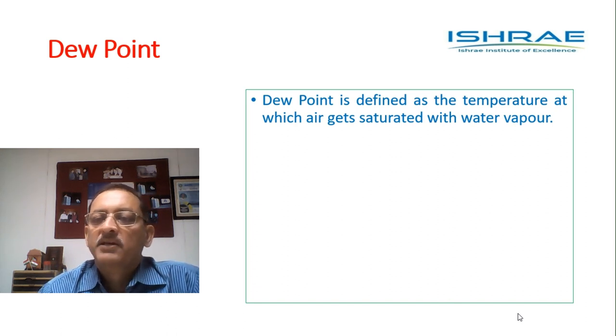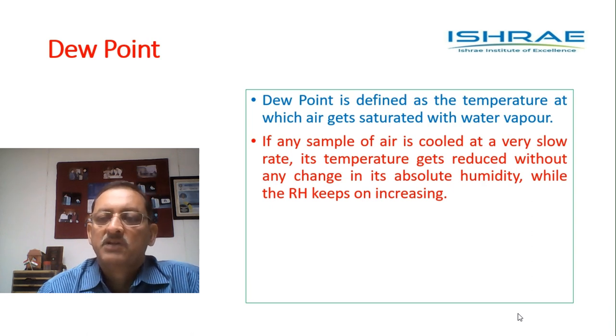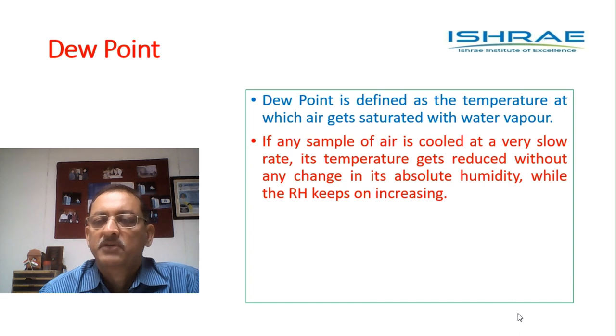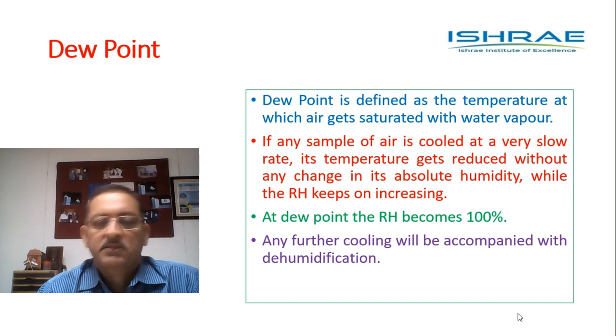Dew point is defined as the temperature at which the air gets saturated with water vapor. If we start with any sample of air and cool it very slowly, the temperature gets reduced without any change in absolute humidity — that means moisture does not come out, dehumidification does not take place. In this process, as temperature reduces without dehumidification, the relative humidity keeps increasing until it reaches 100%, at which point any further cooling will lead to condensation.